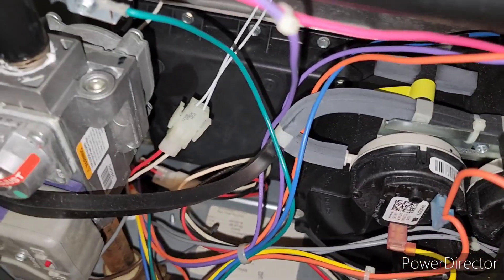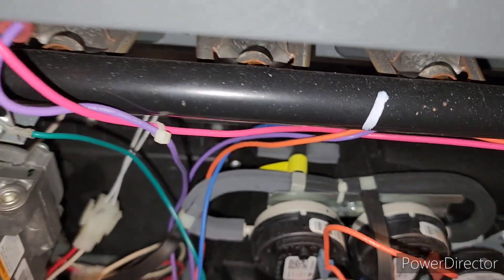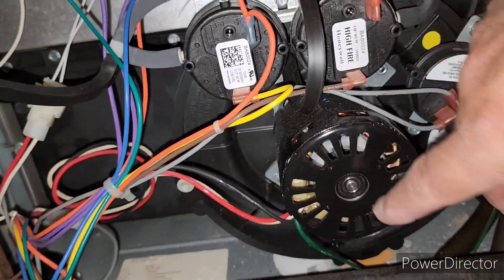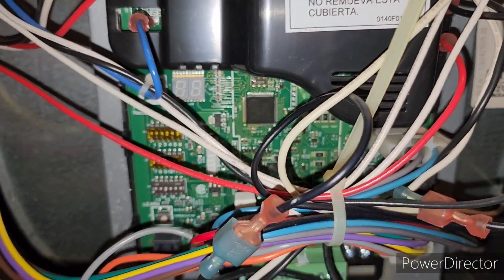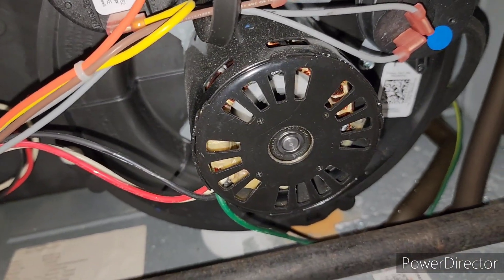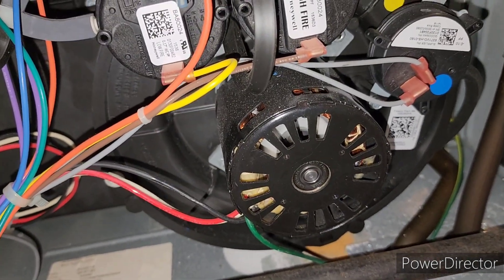I just plugged the igniter back in. I'm going to flip the AC switch on. Typically what happens is this motor right here should start to spin like it is. And then down here it's going to blink H for heat mode. But this morning this was not spinning. But definitely those bearings are going bad.